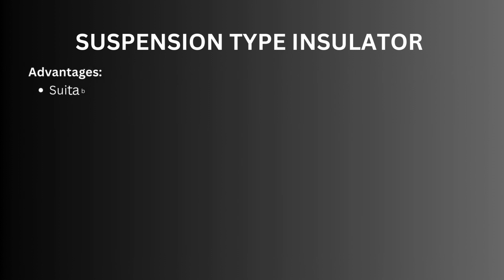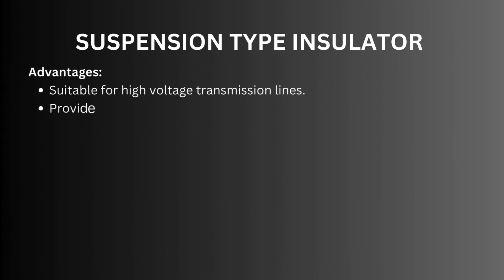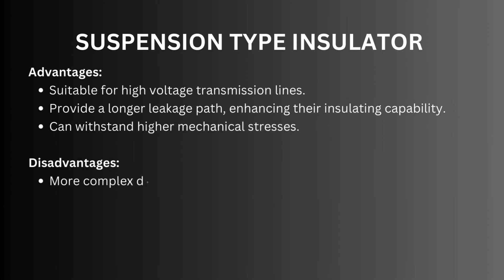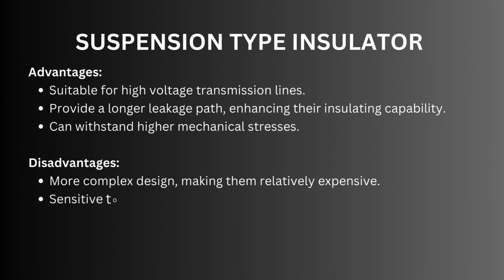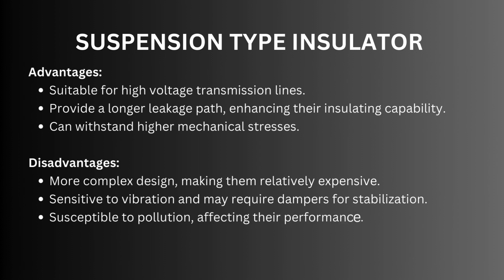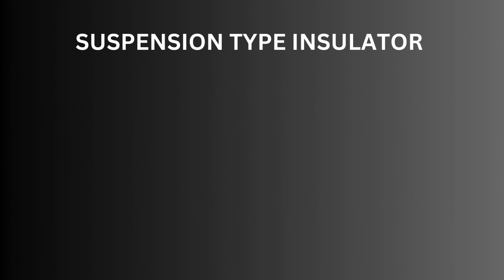Advantages of suspension type insulators: suitable for high voltage transmission lines, provide a longer leakage path enhancing insulating capability, and can withstand higher mechanical stresses. Disadvantages: more complex design making them relatively expensive, sensitive to vibration and may require dampers for stabilization, and susceptible to pollution affecting their performance.